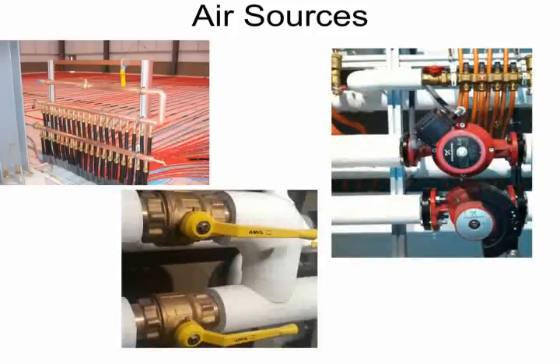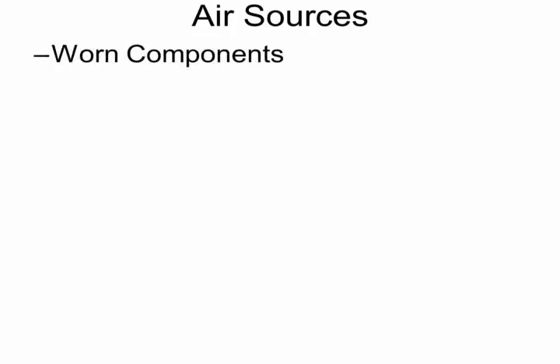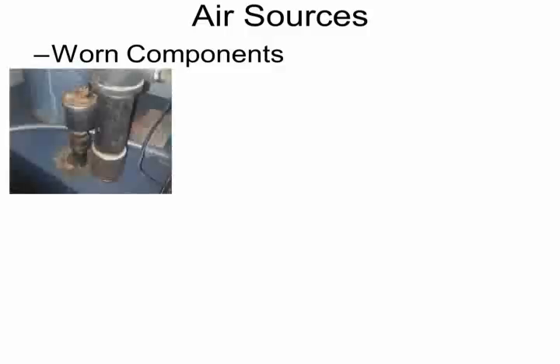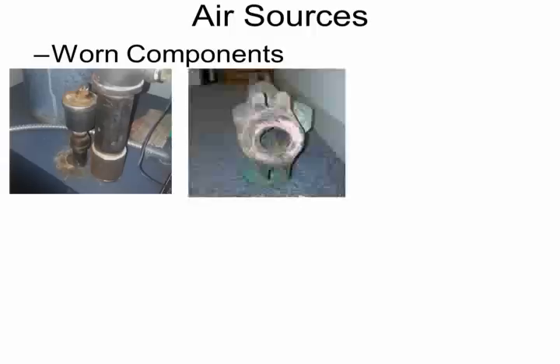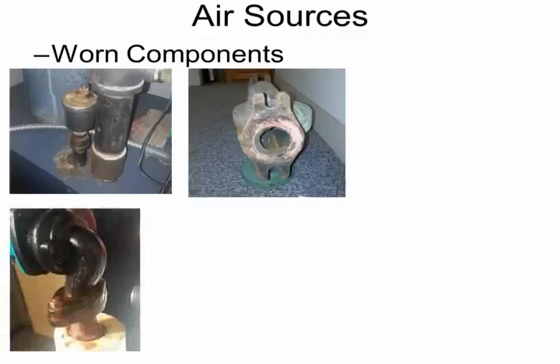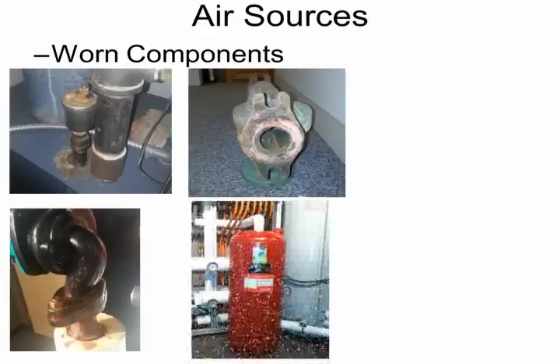And then, in general, anywhere you have a connection of a part to another part is a source for air to get into. Maybe not very quickly, but if fluid can get out, assume air can get in. And that becomes especially pronounced as the system begins to age. So as our systems get older, parts start wearing, air vents start losing, in some cases, water. Pumps can start bleeding water through the flanges. We can get rusting on some of our system from improper insulation that could cause eventually a little bit of water leaking out.